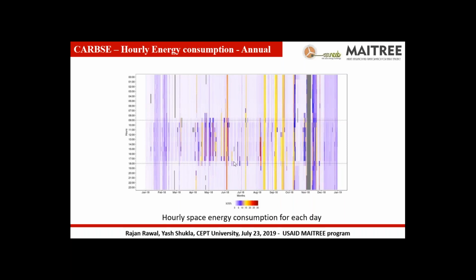Starting from mid-April to July is when we use a lot of energy. But also during the summertime, we have to use a lot of energy to counter the latent loads, or the moisture loads, that come during the monsoon season. So you will see a different kind of behavior of the same building. To counter the moisture load, we have to start running the VRF systems, because the radiant system primarily caters to the sensible loads, or only the temperature, but for moisture load we have to turn on the VRF system. So there is an additional energy consumption you will see in the months of August and September.